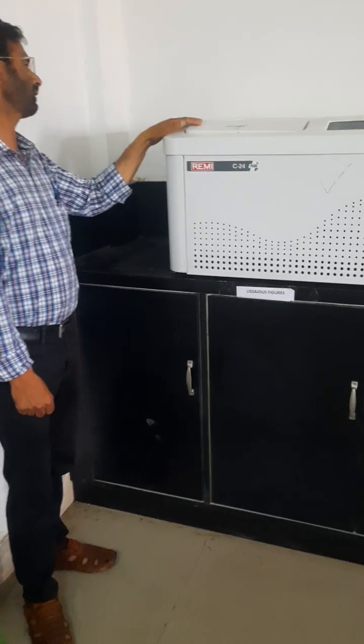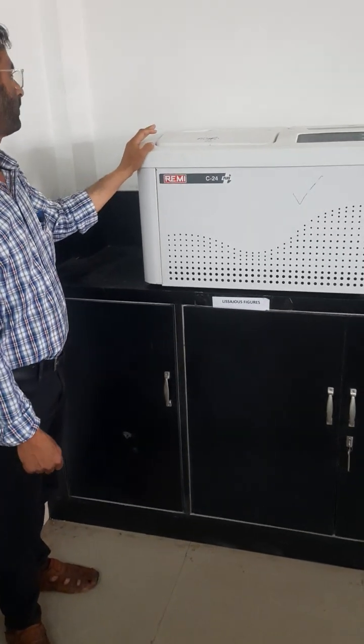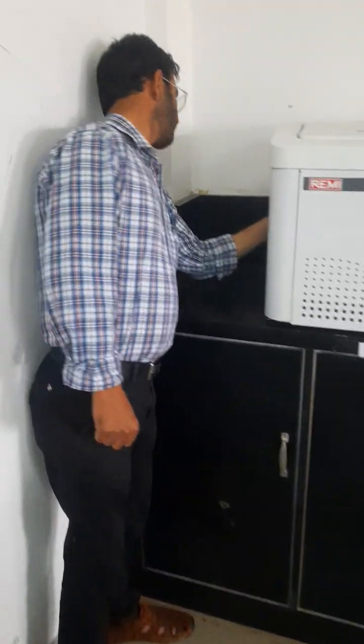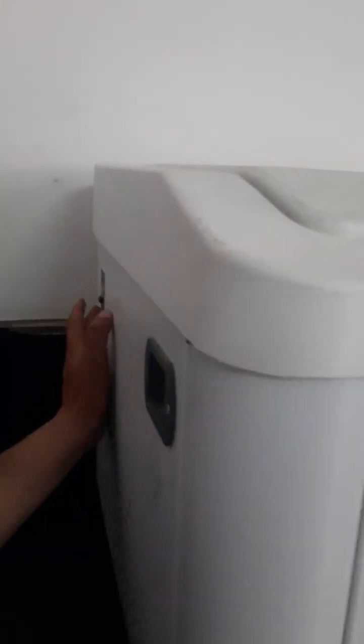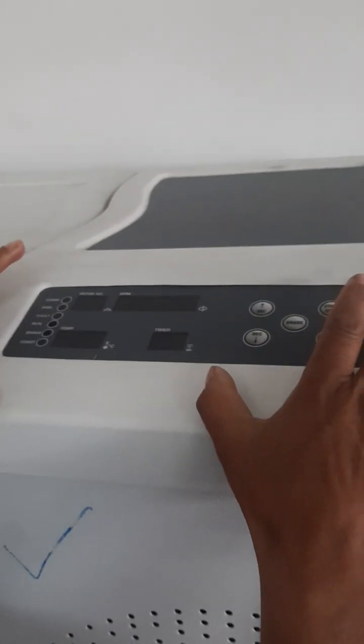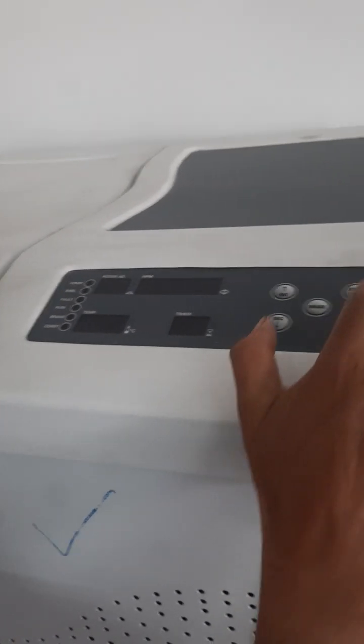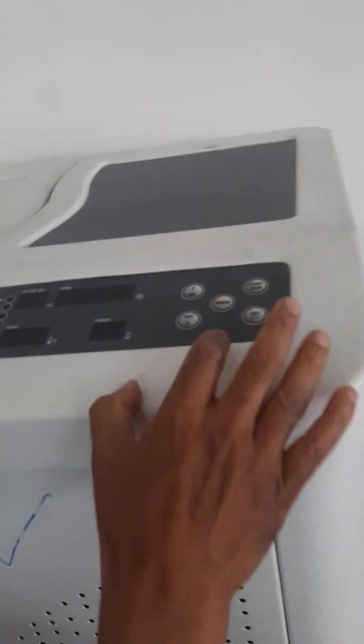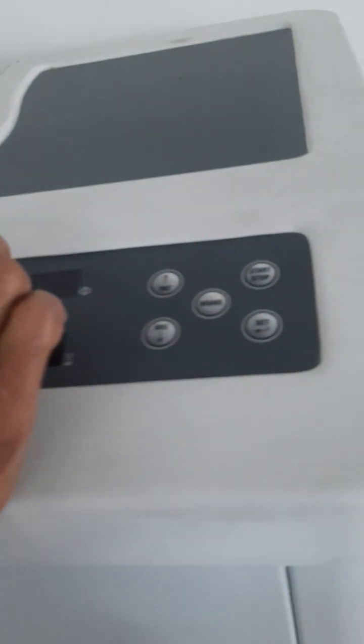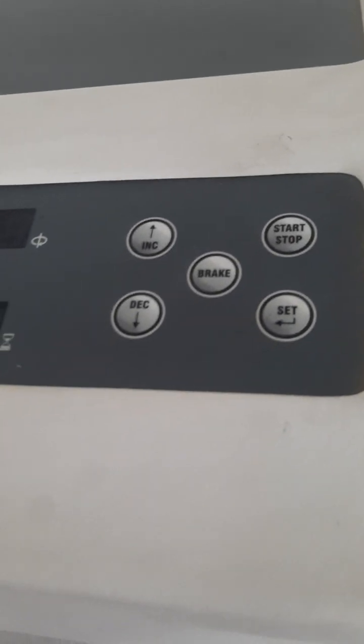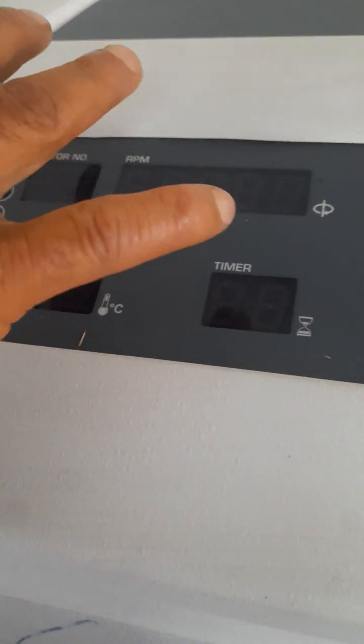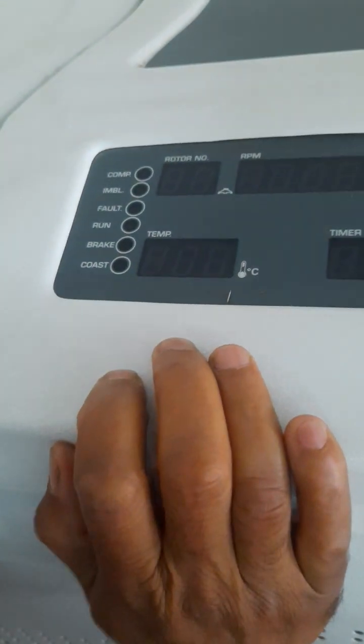So we are starting the component wise function of the centrifuge, how it is operated. This is the centrifuge. Here is the main supply, the mains where we can switch on this machine. This is the opening latch for opening the lid, and here is the LED display where we can have the reading. We can set the machine, we can start, we have the brake, we have increase and decrease of what we set here. We set rotations per minute, we set rotor number, we have this calibration. It reads whether our centrifuge works normally or not, whether it is running, in fault condition, or has imbalance in the rotor, etc. And we have this display for measuring the temperature that we set here.